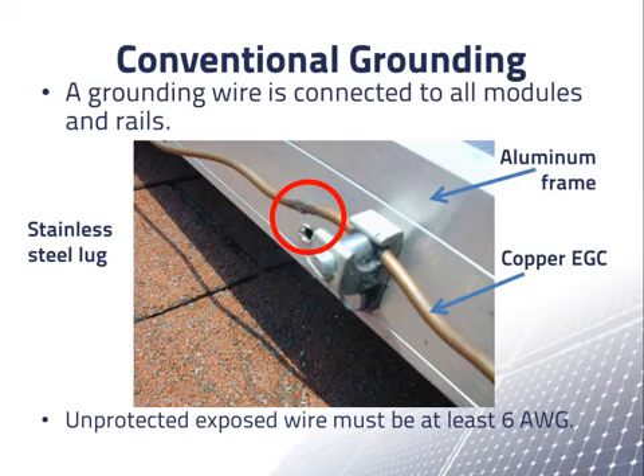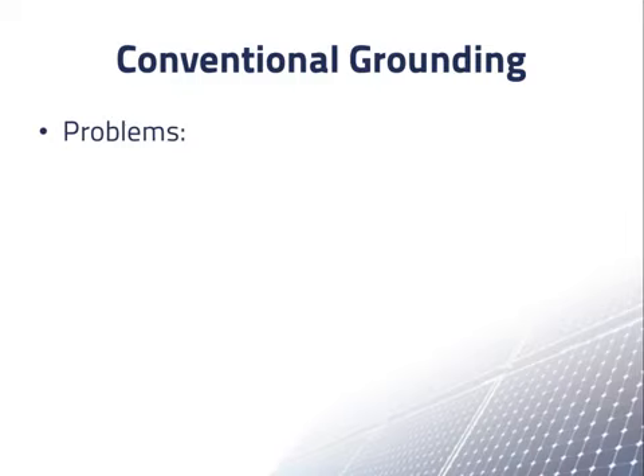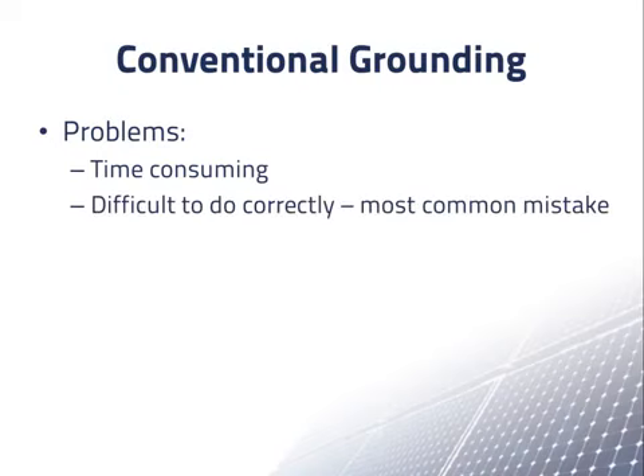The exposed metal parts of many PV systems are connected to ground as shown in this picture. However, there are several problems with doing equipment grounding as shown here. The problems include that it is very time-consuming to run all of these ground wires all over the array, and it is difficult to do so correctly. The most common mistake found in PV systems is improper equipment grounding. Lastly, the copper wires are unsightly if they are visible. You can do your best to keep the wires under the modules or someplace else out of sight, but they're usually visible someplace.